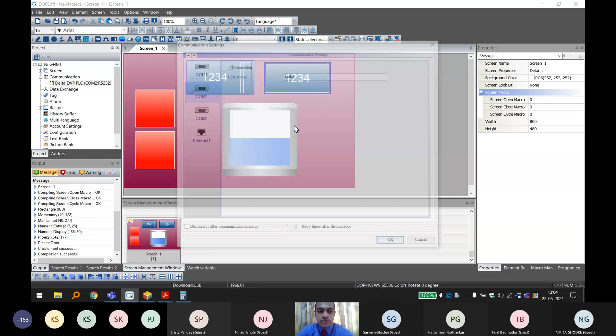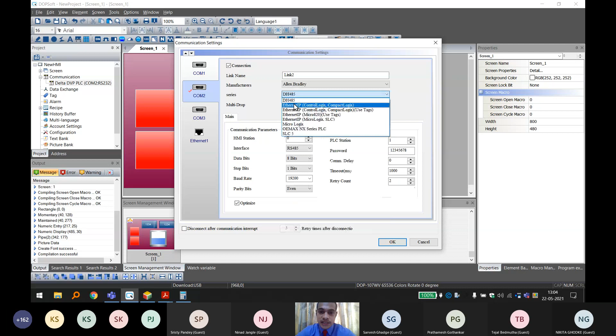Can we use Delta HMI on other PLCs like Allen Bradley? Yes, you can. If you go to the HMI and click on add device, you'll see different options. In the manufacturers tab under communication settings, it supports many different types of devices, like Siemens, Toshiba, Omron, Mitsubishi, Keyence, Hitachi, Fuji, Emerson, Beckhoff, Allen Bradley, and so many other PLCs. You just select it and then select the particular PLC you want to communicate with, so yes, it does support it.